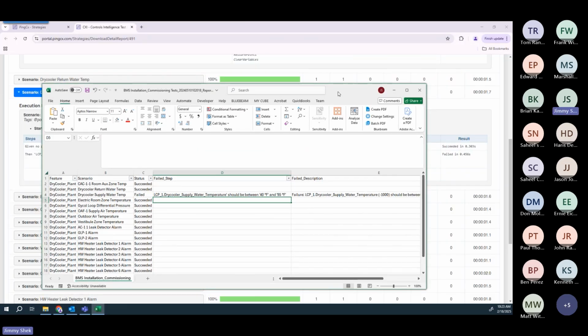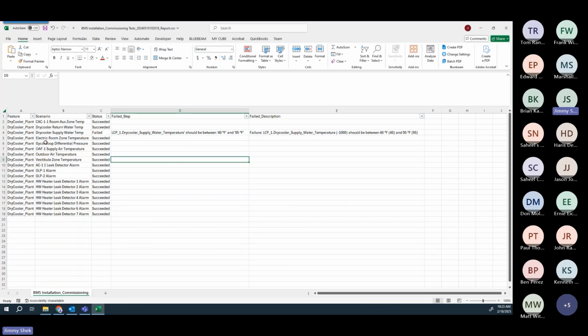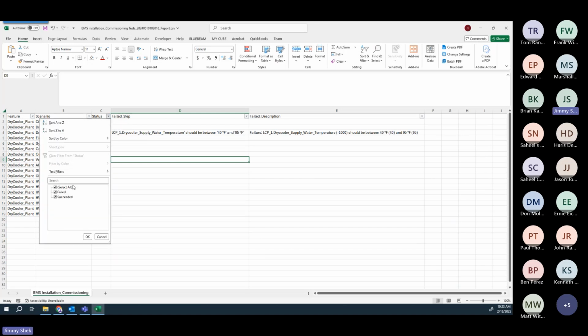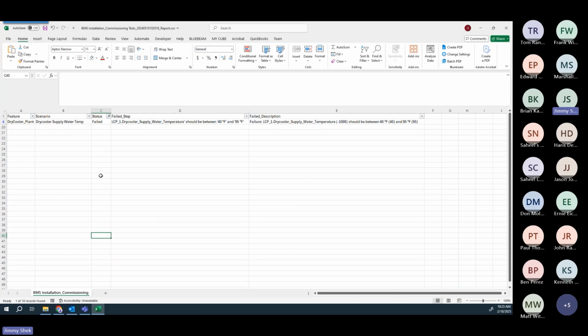So one of the other reports that we generate is more of a punch list style report. In this case, it's the same feature file. You see the same scenario, and you have the ability to filter inside Excel to look at only your failed scenarios. Here, obviously, it's a very simple example of just the one dry cooler plant with the one failure. But you can imagine if this test was scheduled for hundreds of VAV boxes, hundreds of units, with dozens of failures. Now you essentially have a punch list that a technician can use to start the investigation. Instead of manually connecting to each one of those VAV boxes and manually checking each one of those sensors, you can have PingCx do the heavy lifting and save the time of someone manually doing these checks. Now you can work off that punch list and start looking at just the issues and errors that were reported after the test.